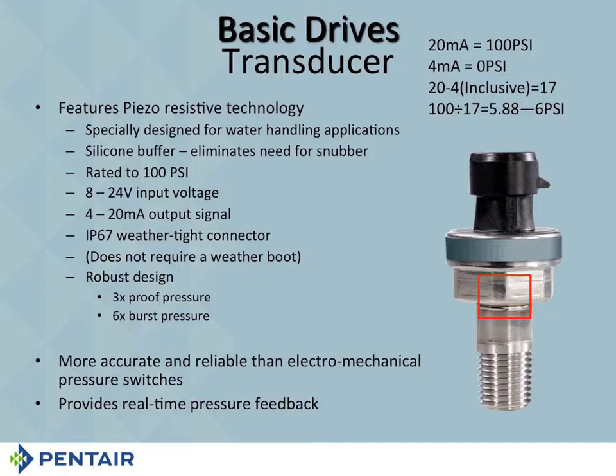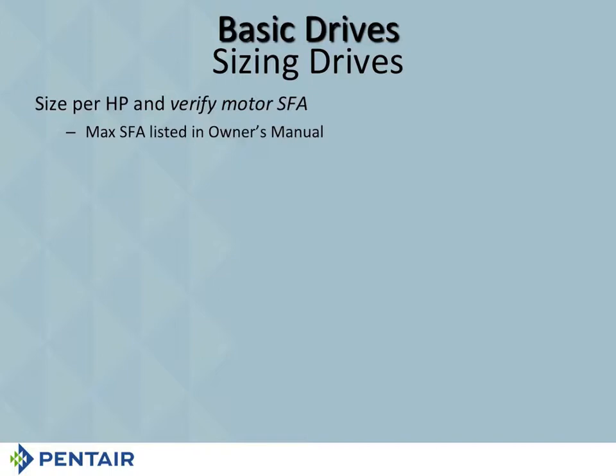Okay? So when it comes to sizing a drive, you'll notice it first says size per horsepower and verify service factor amps. Remember what I said, size per service factor amps. Don't get excited about horsepower. Horsepower isn't really important. What's important is those service factor amps. If you can cover the service factor amps, you're going to be just fine. Okay? The max load or service factor amps are going to be listed in the owner's manual.